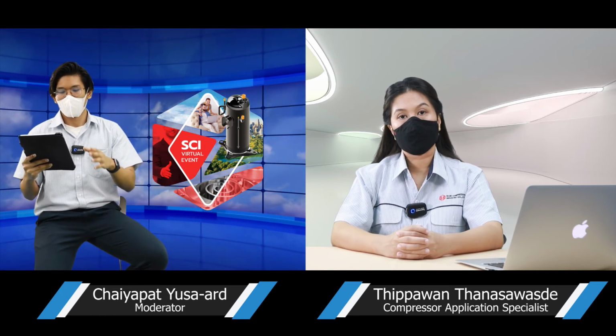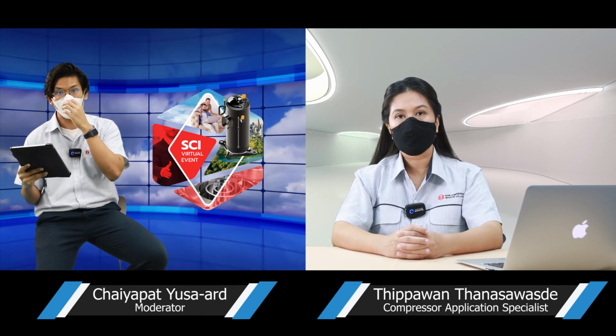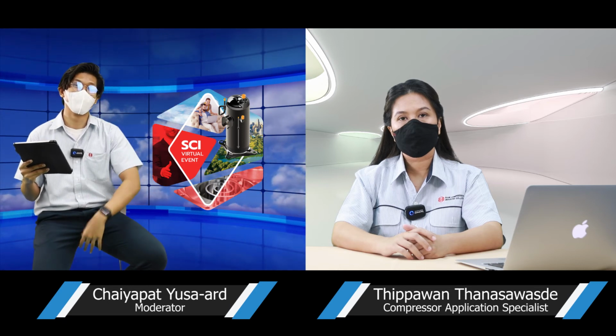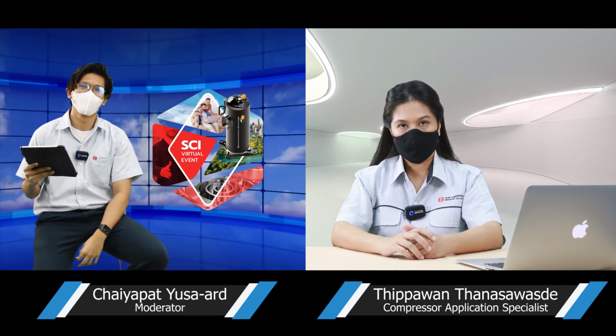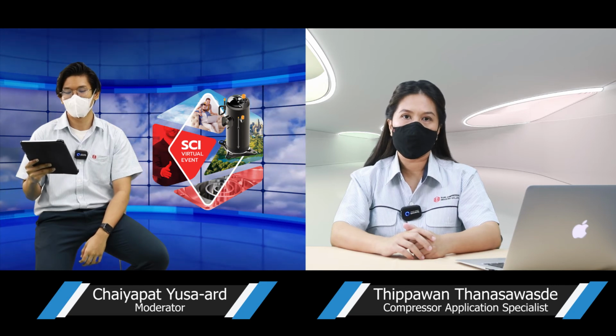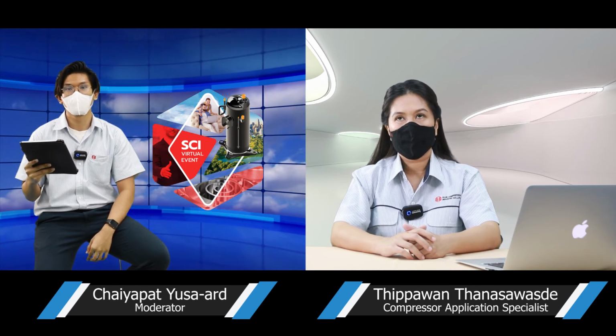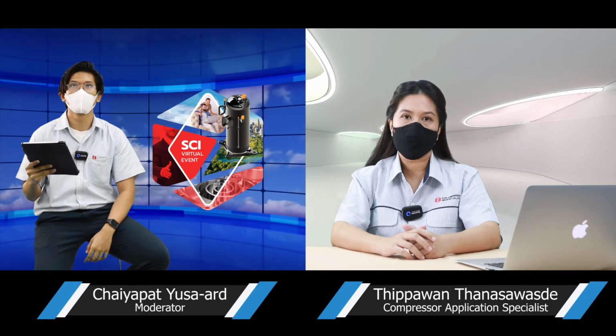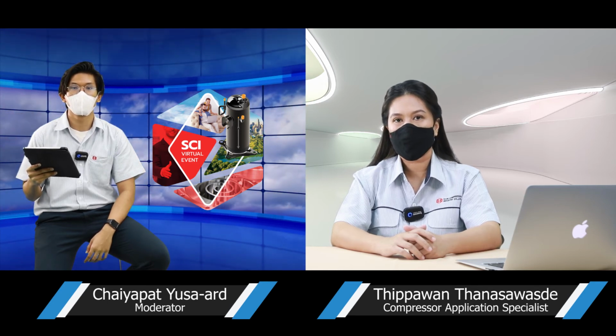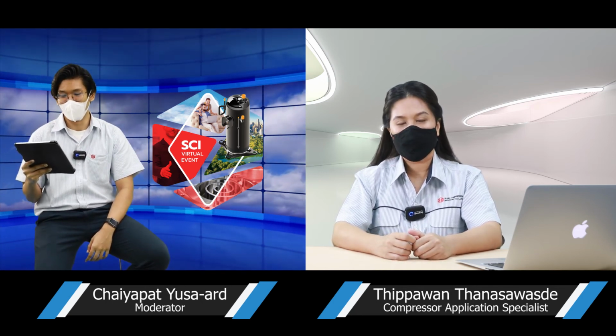what is the minimum ET of the 128cc that can be operated? I think that they want to know if they will use our compressor in very cold conditions. And the lowest evaporating temperature of our 128cc is minus 30 degrees Celsius. This is approximately an ambient temperature of around minus 20 to minus 25 degrees Celsius. Oh wow, that will cover, I think, almost all the conditions. That's quite low in temperature.